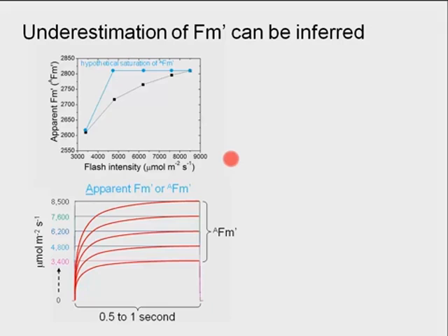That's a good question. So what I mentioned is that there are problems with the flash intensity from an instrumental point of view as well as a physiologic point of view. And let's deal with the instrumental point of view first. If you're applying voltage to an LED to cause it to illuminate, that LED is going to heat up, and the dies in those LEDs are going to lose their efficiency at those high intensities. And so there are problems in one sense with keeping the LEDs at a constant intensity, and if you increase the duration of the saturation flash, you're going to run into those types of problems. Now that's instrumentally, that's just one example.